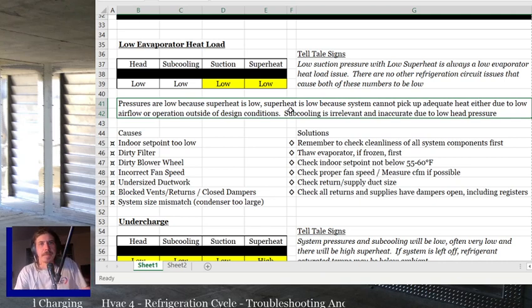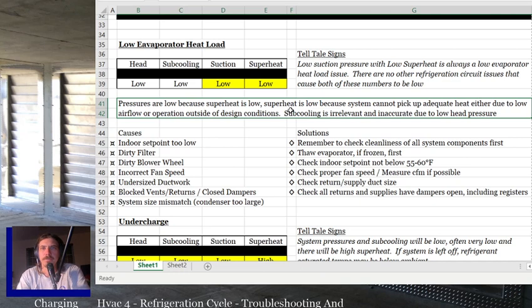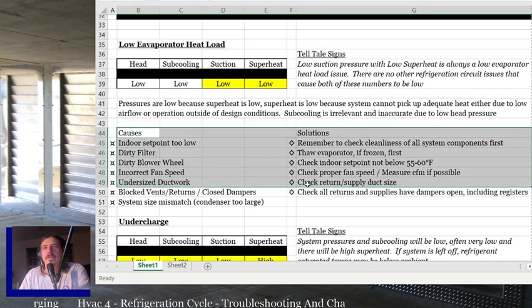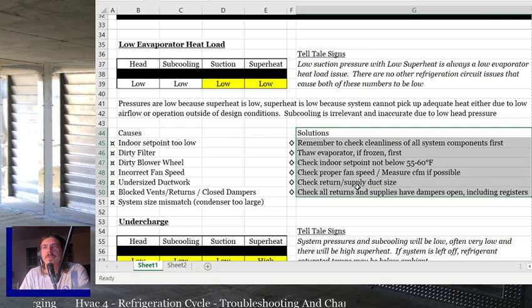Going back to thinking mechanically, what's more important than knowing what these should be is knowing why they are what they are. So it's not really that important to remember that low evaporator heat load is low suction pressure and low superheat. It's better to try and know why low evaporator heat load is low suction pressure and low superheat. And we're going to go through those, and then I'll give you some possible causes, some possible solutions.